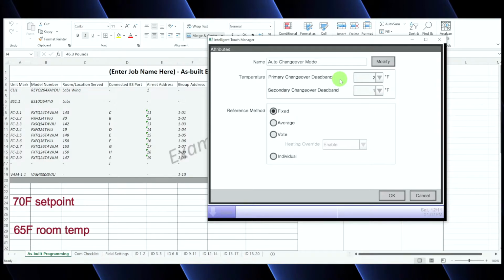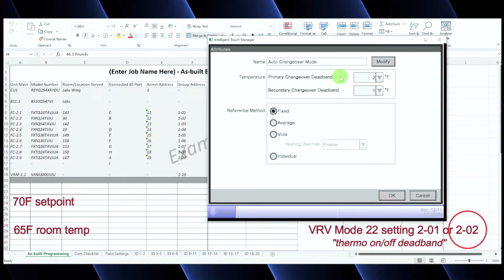So it's going to heat to 70 degrees. And depending on how you set up the field settings, from previous videos, we've talked about this before, you can have either a 1 degree or a 2 degree Fahrenheit deadband. We like to program a 1 degree Fahrenheit deadband. That way, as soon as the room temperature gets to 71, it satisfies. So based on how you program that thermo on-off deadband, you need to come in here and set up your primary changeover deadband. If you have a single set point application, where your set point is 70 for heating and 70 for cooling, then you're going to need at least a 2 degree primary changeover deadband.